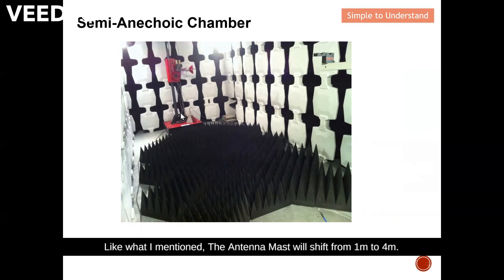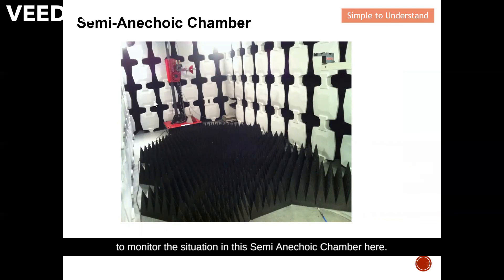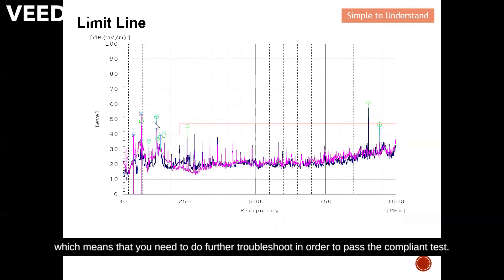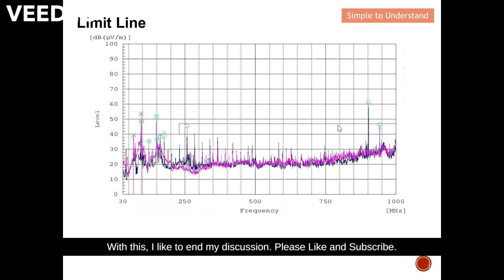This photo is taken from the turntable. You can see the antenna mast, which shifts from one meter to four meters. Here you can also see the camera used to monitor conditions inside the semi-anechoic chamber. This is the limit line for CISPR 22, shown in red. Any measured point that exceeds this limit line means further troubleshooting is required to pass the compliance test. To pass the EMC compliance test, all measured points must be below the limit line. Please like and subscribe — thank you so much.